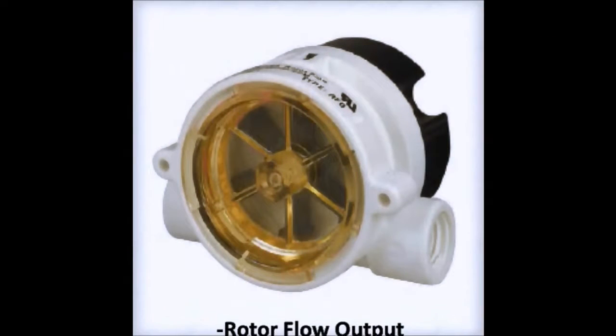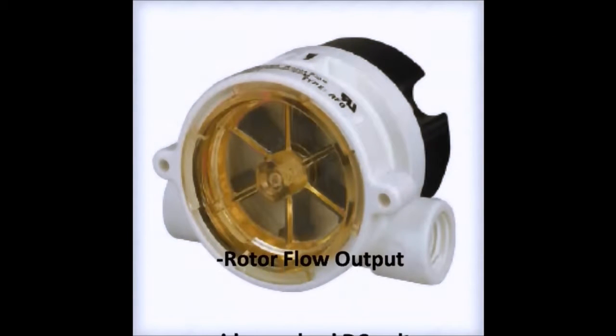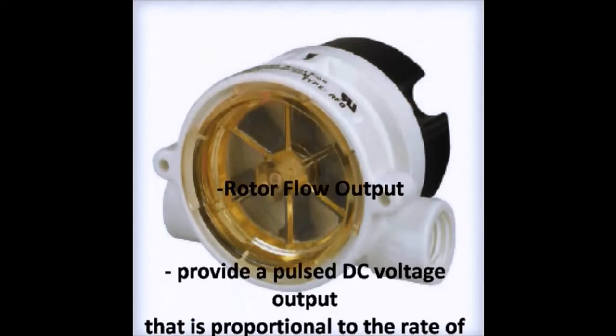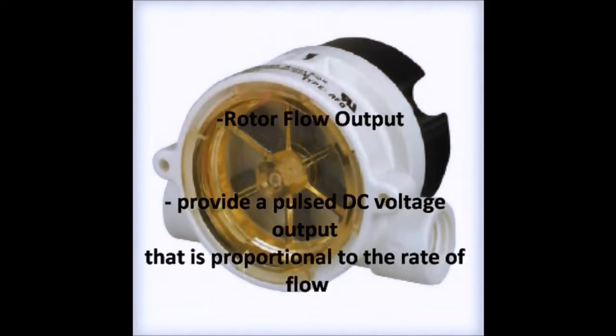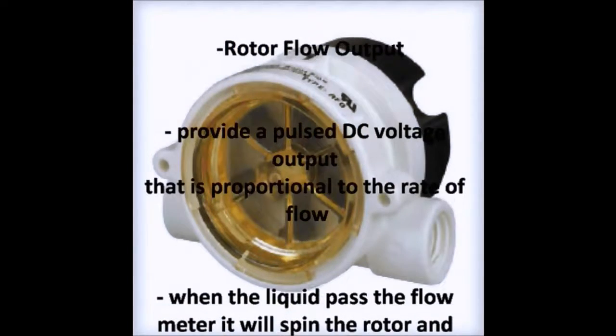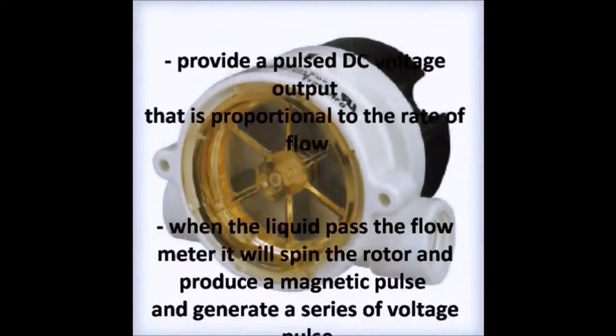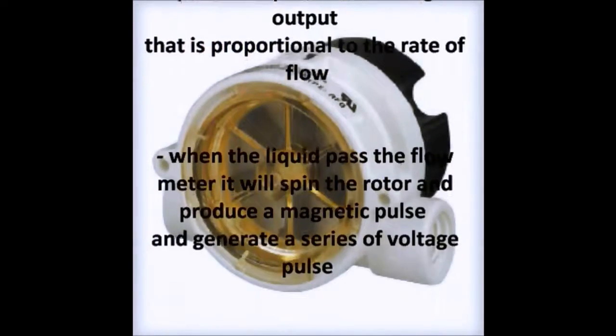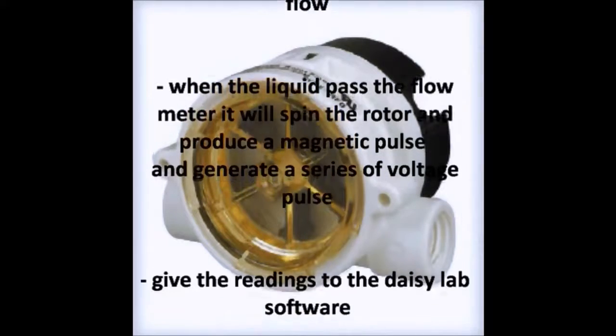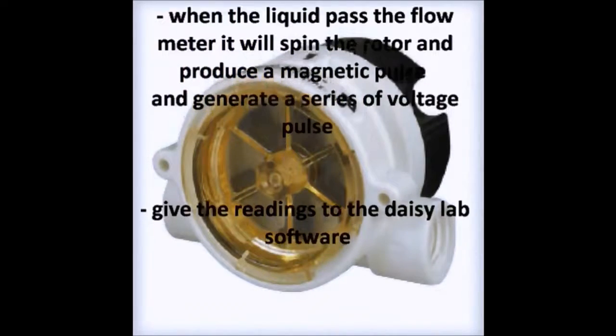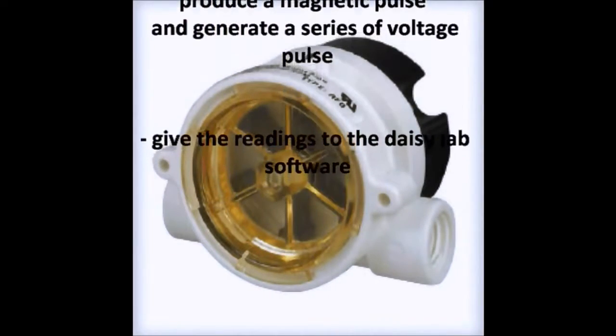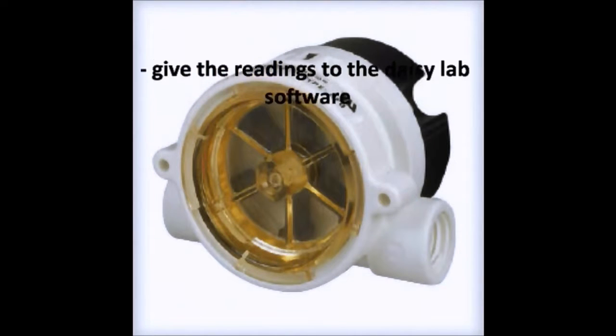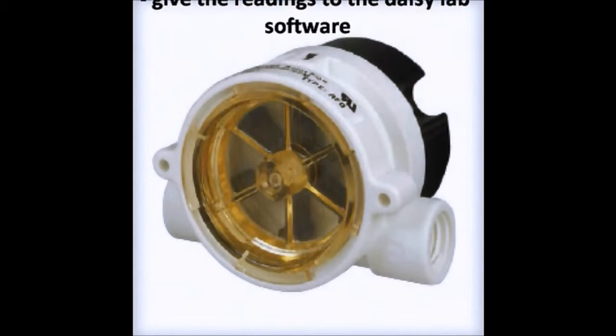The flow meter that we have in the Fluid Mechanics Lab is known as a rotor flow output. It will provide a pulse DC voltage output that is proportional to the rate of flow. When the liquid passes the flow meter, it will spin the rotor and produce magnetic pulses and generate a series of voltage pulses. This will give the readings to the DaisyLab software.